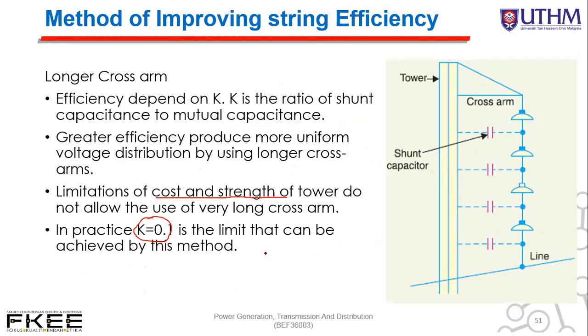So the method for improving string efficiency is, first, we can use a longer cross arm. Efficiency depends on K, where C1 equals KC. So K is the ratio of shunt capacitance to mutual capacitance. Greater efficiency produces more uniform voltage distribution by using a longer cross arm. If we use a longer cross arm, it is better, because we reduce the shunt capacitance. But limitation of cost and strength of tower do not allow the use of very long cross arm. In practice, K equal to 0.1 is the limit that can be achieved by this method.